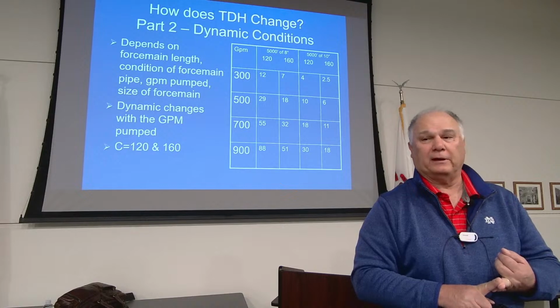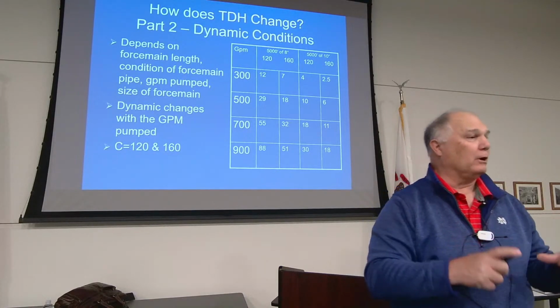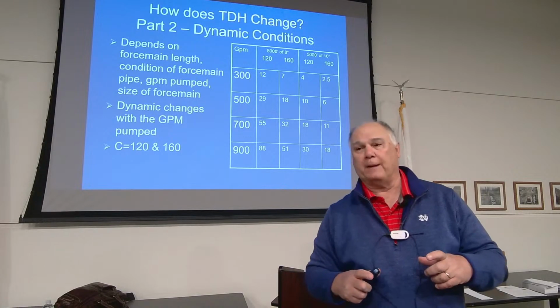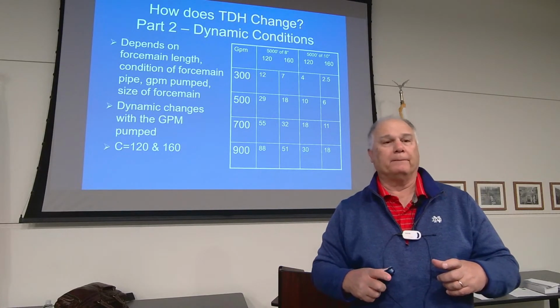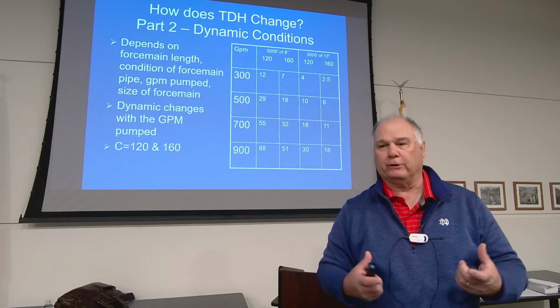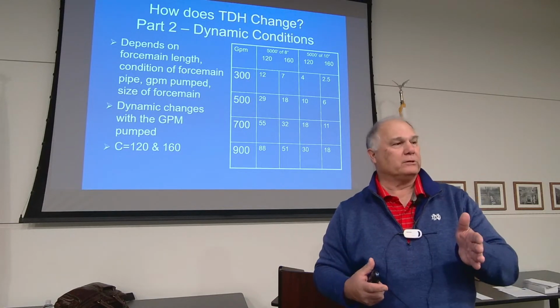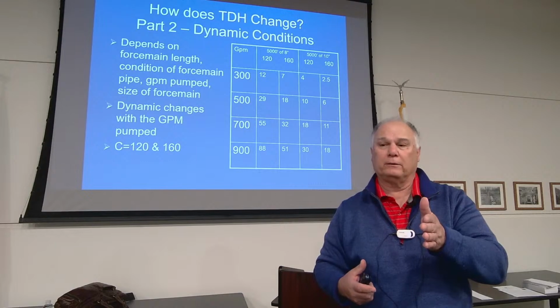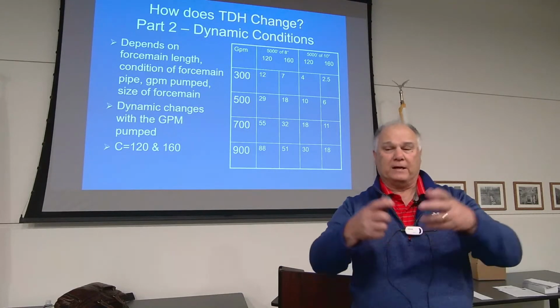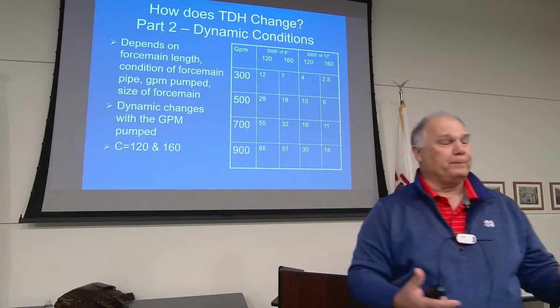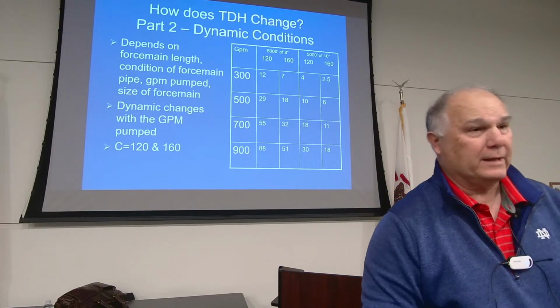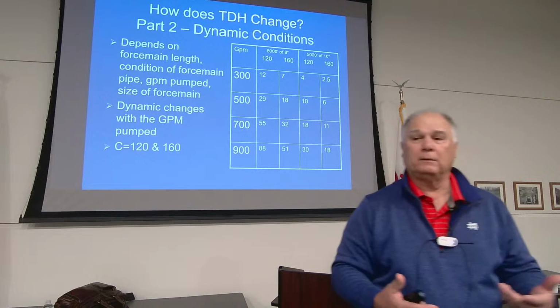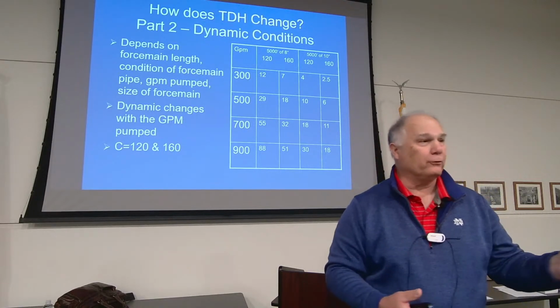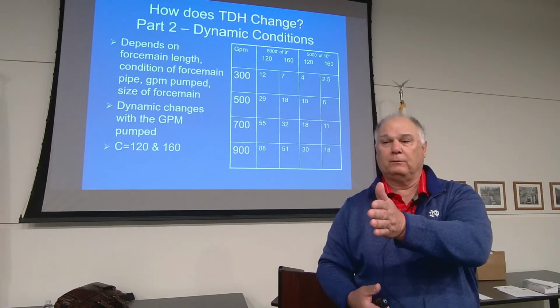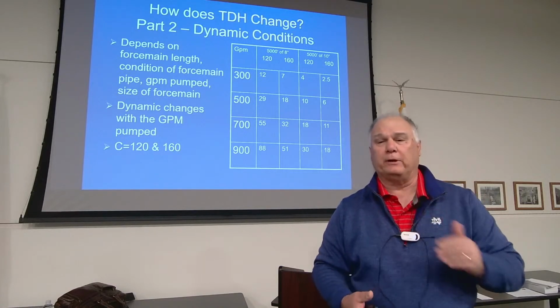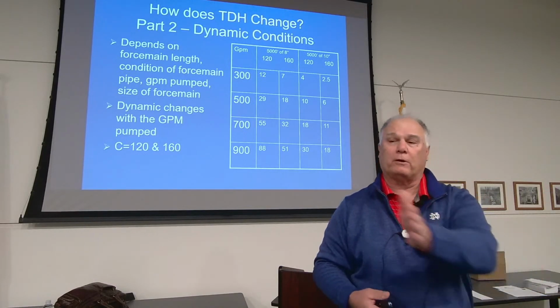It's going to look pretty old, Barnacle Bill is what we usually call it. It's going to have a whole bunch of crap stuck on the side, and it's just not going to look very good. So as we pump through that, what's going to happen? That friction is going to be higher because it's not smooth. But a brand new PVC pipe is going to be as smooth as a baby's butt. Then stuff is going to go through there like a rocket with less horsepower, less energy that we have to put into the pump in that station to get that water out of there.